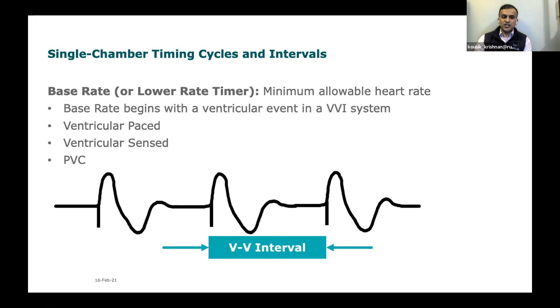If it sees intrinsic activity, it says, okay, the heart rate is above 60, I'll start another timer. So it's beat to beat monitoring, not an average of 60 beats over a minute. It's literally that every beat has to be 1,000 milliseconds after the last either pace beat or the last intrinsic QRS.